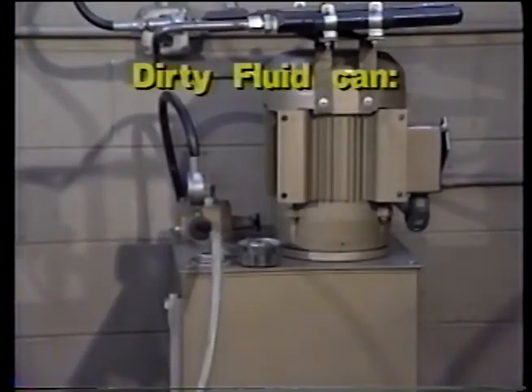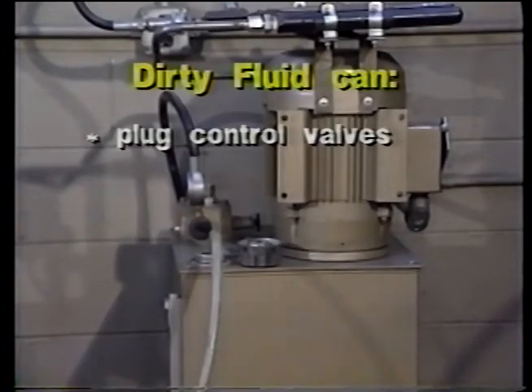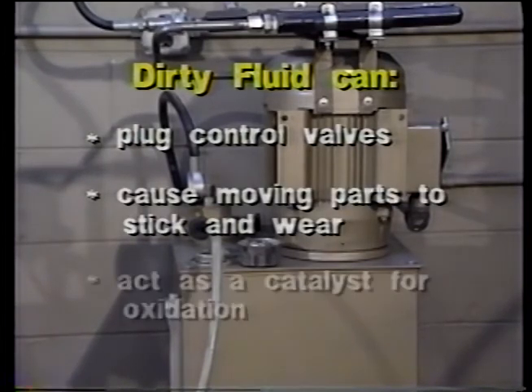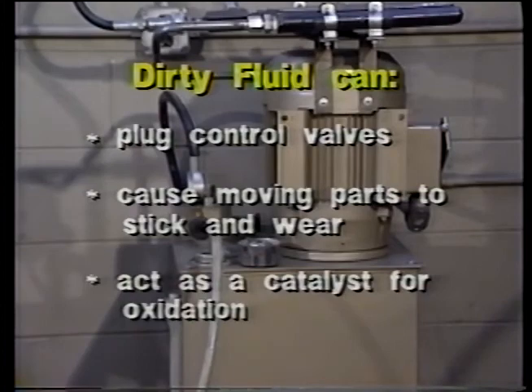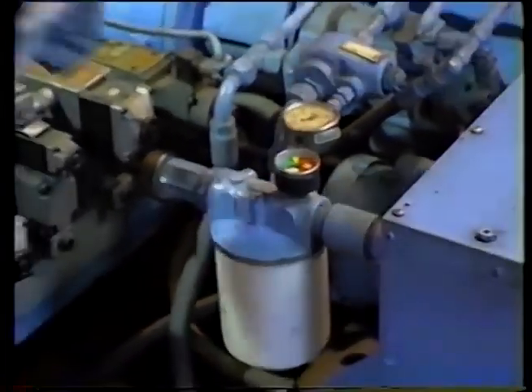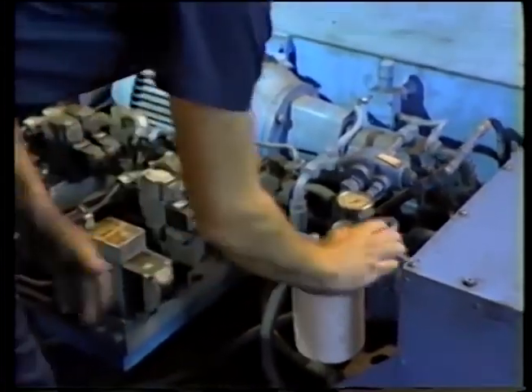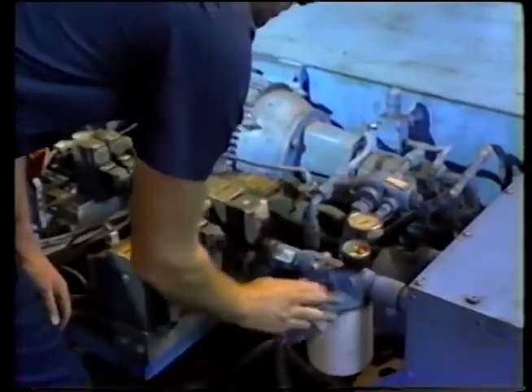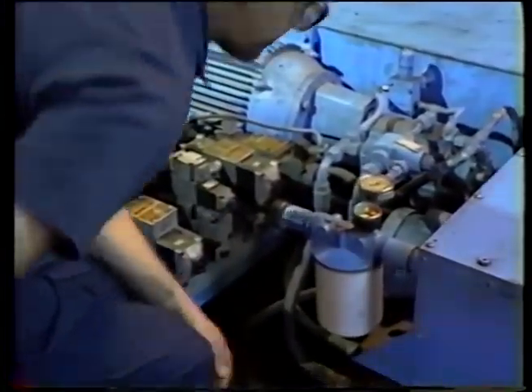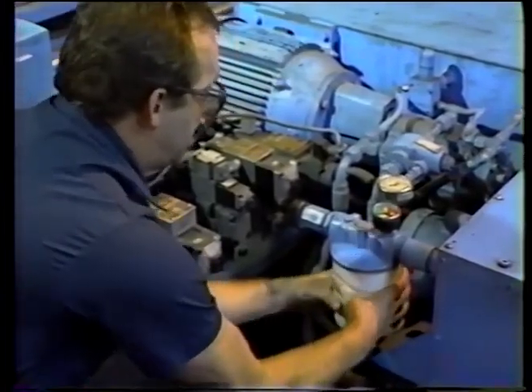Dirty hydraulic fluid can plug up many kinds of control valves. It can cause moving parts to stick and wear excessively, and it can act as a catalyst for oxidation. Inspect your system's fluid frequently for contamination and keep any filters serviced regularly. If the filter is being bypassed, it needs to be cleaned or replaced.